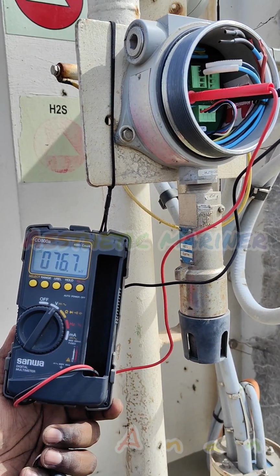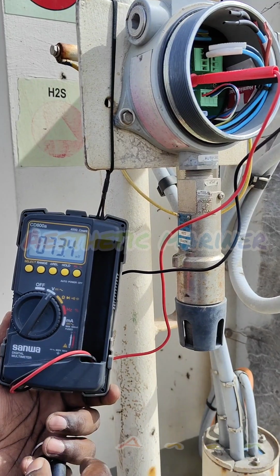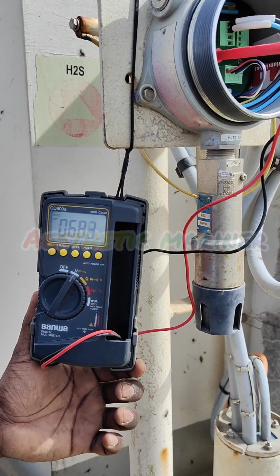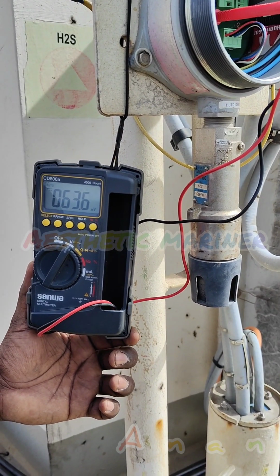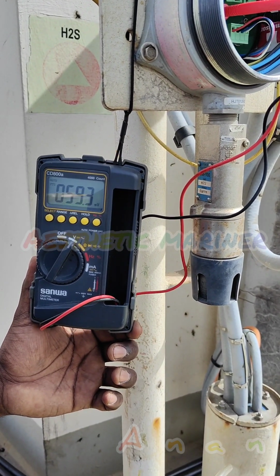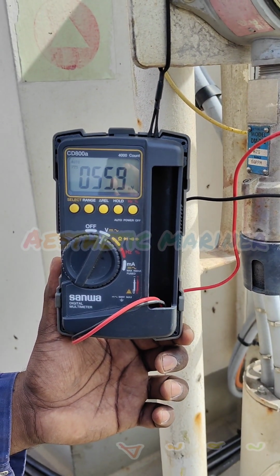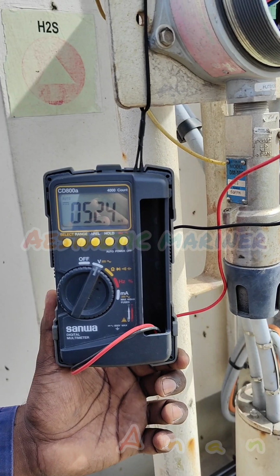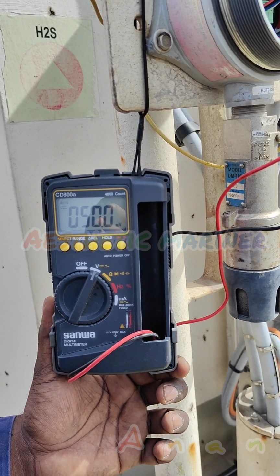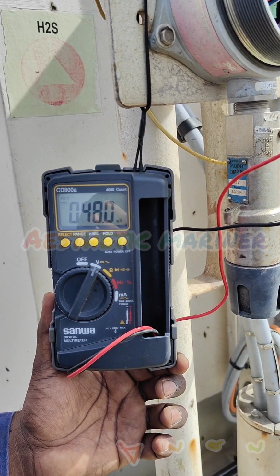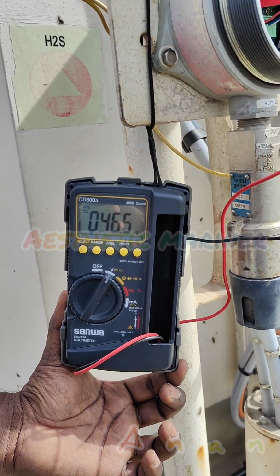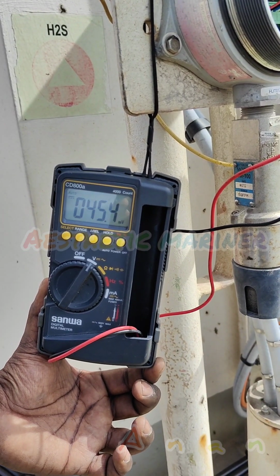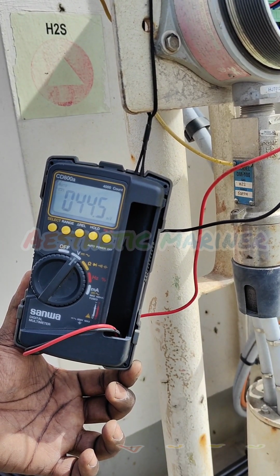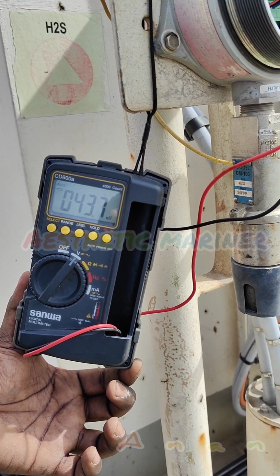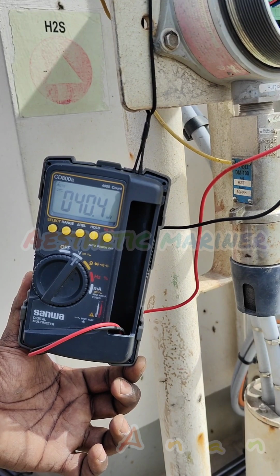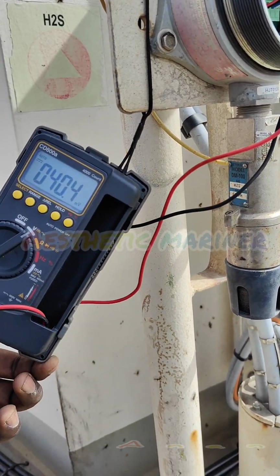Now we can observe the gas reading slowly decreasing because we have already removed the gas. If the span calibration fails, it will go back again to 20 millivolt. Only once it passes will the sensor go back to normal. Otherwise it will always show a faulty sensor. So we need to confirm that the span calibration has passed. Now we wait for the gas to bleed off. It almost reached 40 millivolt. Once it reaches 40 millivolt, we can remove our multimeter and keep the sensor back to normal. Now the sensor is already back to normal.